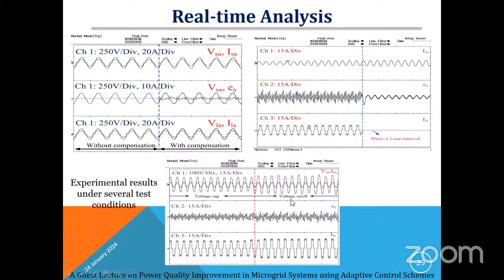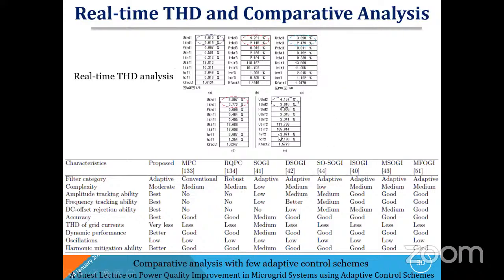Voltage sag and voltage swell also we have given. If you see the result, this is the real-time THD content; these are the THD values we have taken. Here we have given only 5 cases. See the voltage and current THD: 3.2, 4.2, 3.2%. Another condition 3.2, another condition 4.2. That means within 5%. Based on the IEEE standards, the current has to be maintained within 5%, and in every condition we got less than 5%.